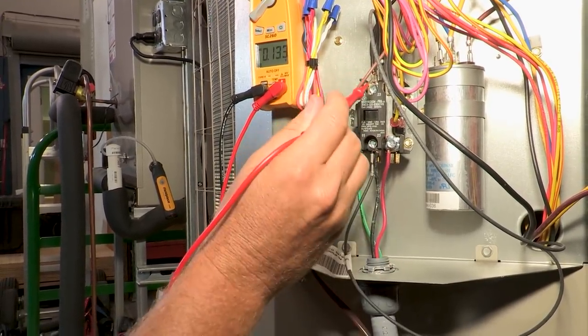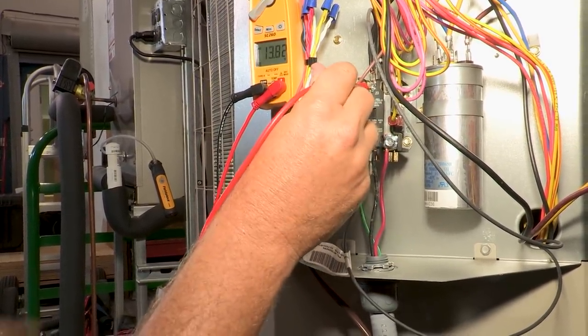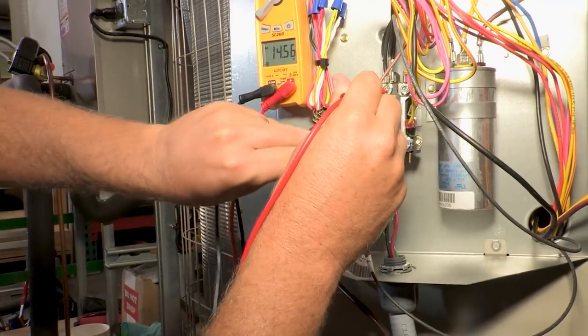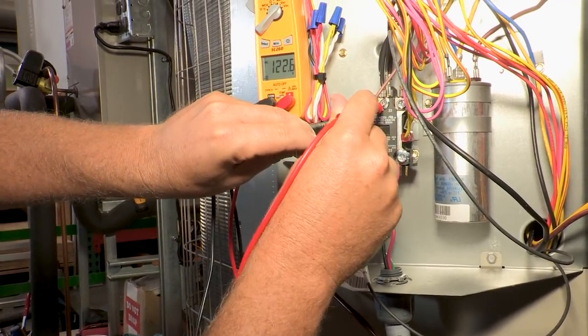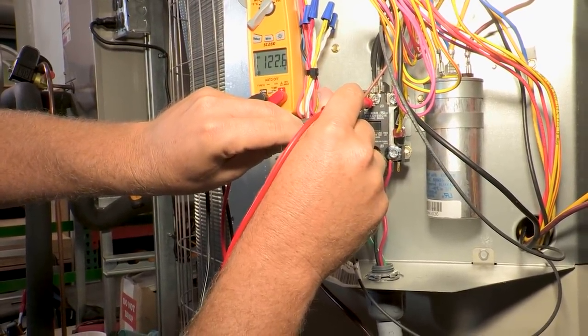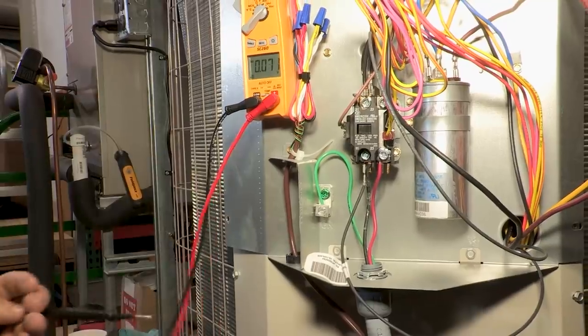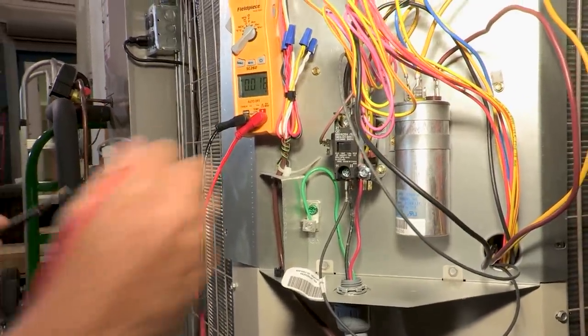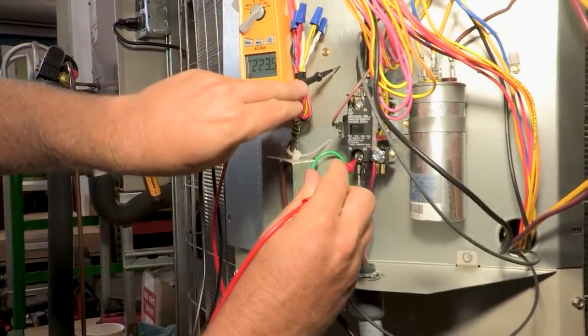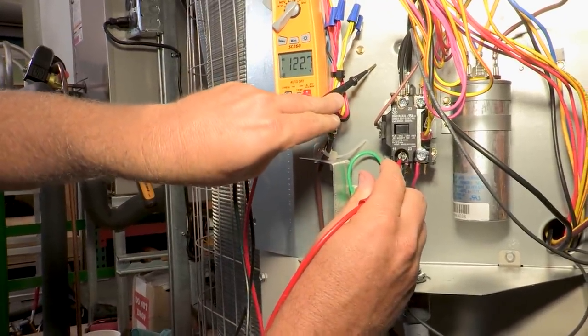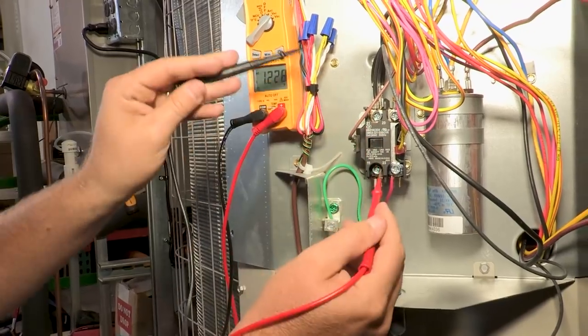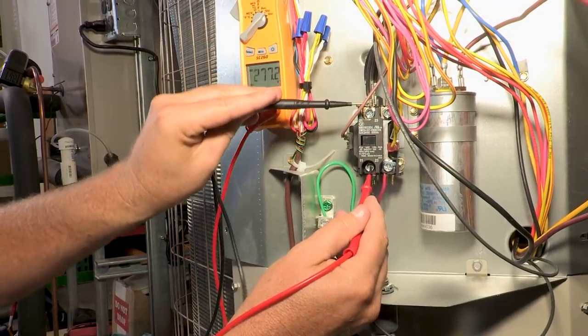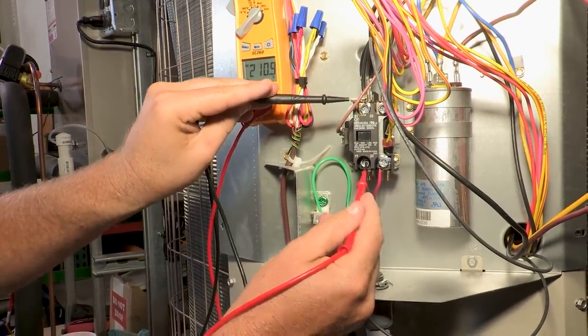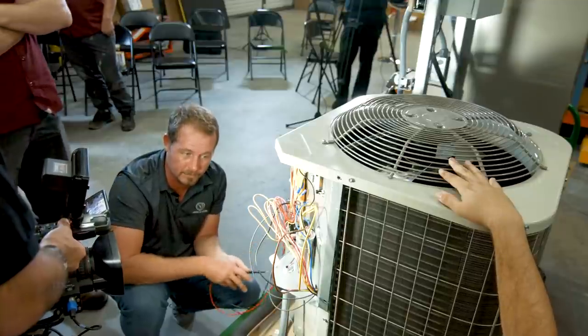So we're actually seeing the voltage that we see here, and we'll go ahead and just show it to ground, even though this wouldn't be a normal test. You see we have 122 volts there. The reason that we're seeing that is because it's backfeeding through all those loads. So I've got 120 volts here on one leg, 120 volts here on the other leg, and then we have 240 across. So it's being fed through the motor windings as well.